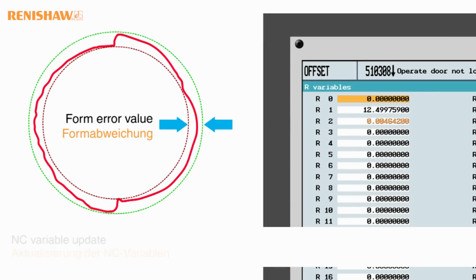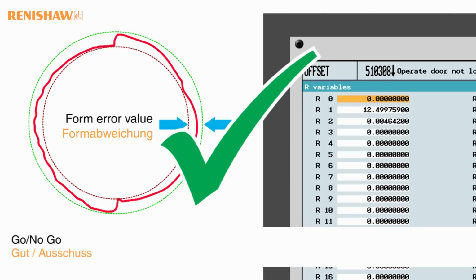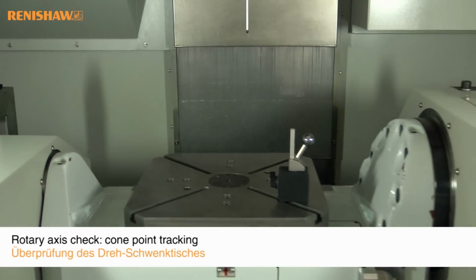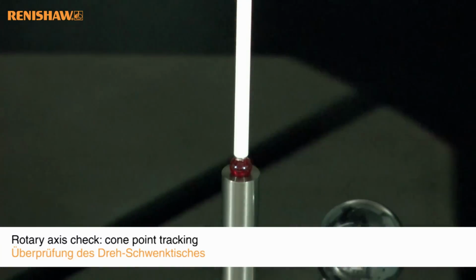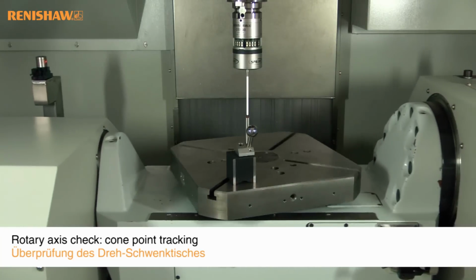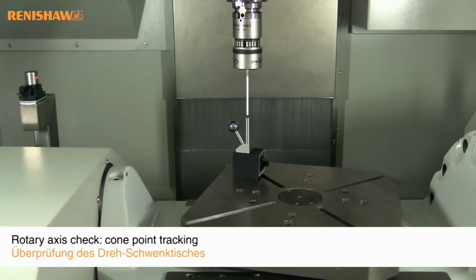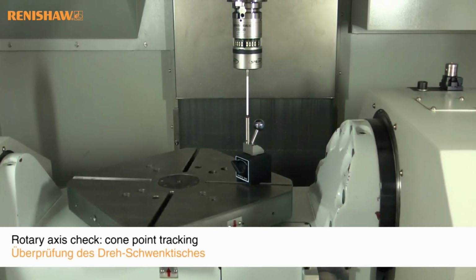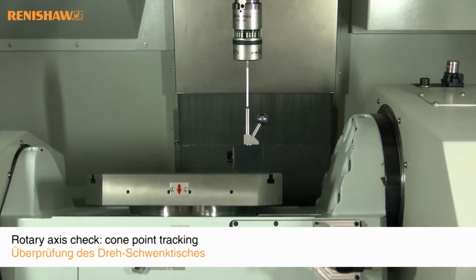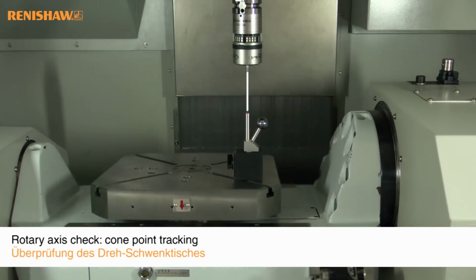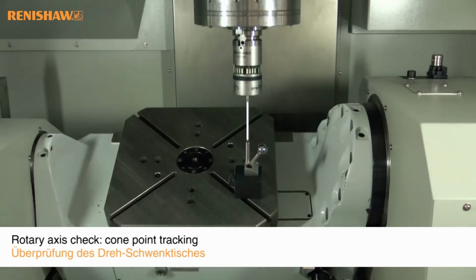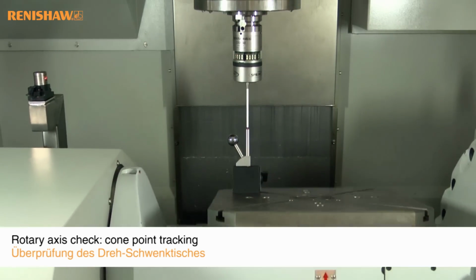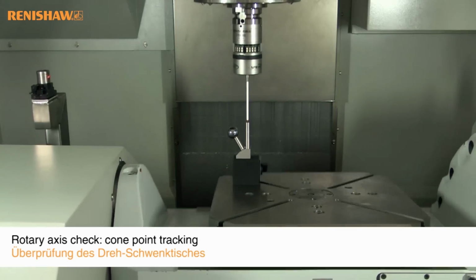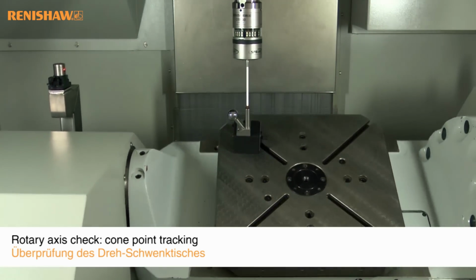It must be noted that we do not update the machine axis information. So this is an output that is just for you to decide whether your machine is ready for machining of the part. For the multi-axis machines, we drive the probe into the cone in the cylinder and then rotate the table in a number of orientations. As you see, the cycles are very quick.